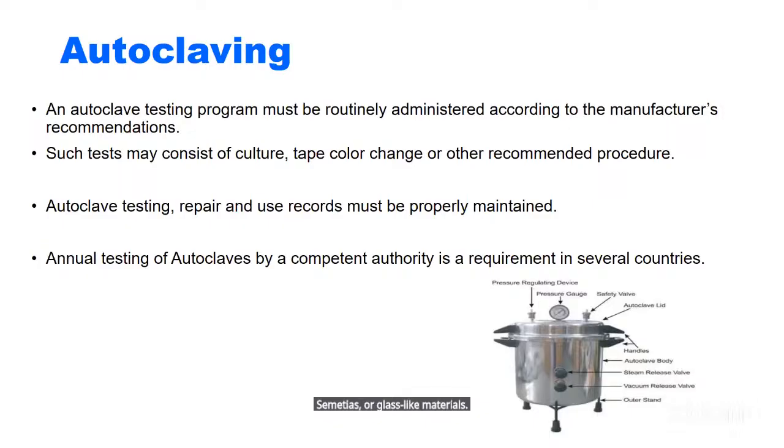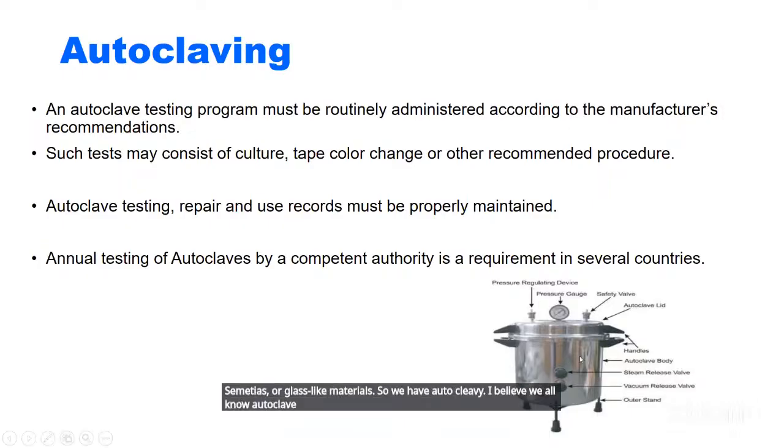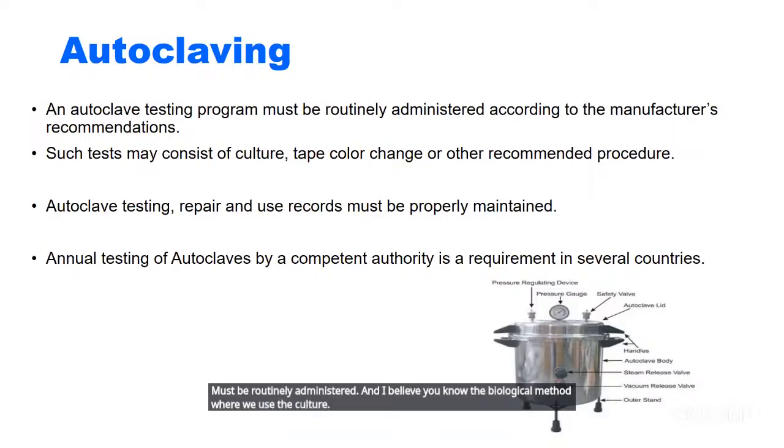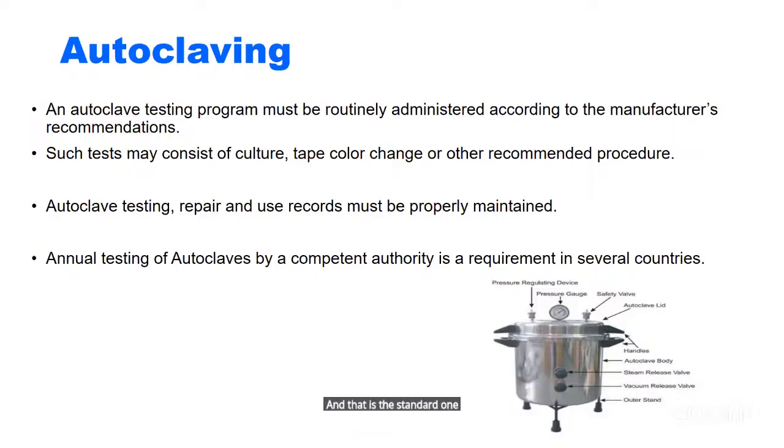So we have autoclaving. I believe we all know the autoclave because we also use it in our laboratory. An autoclave testing program must be routinely administered. I believe you know the biological method, where we use a culture, and that is the standard one. We can also use tape. The setting of the autoclave, the repair, and the maintenance are very key.